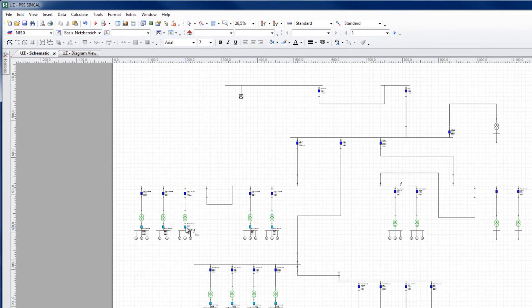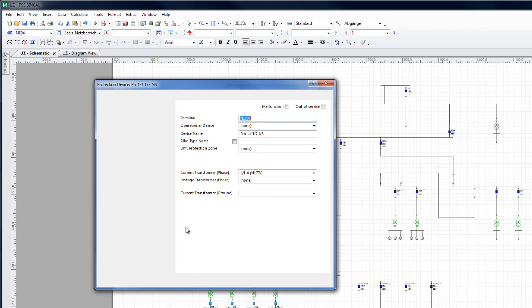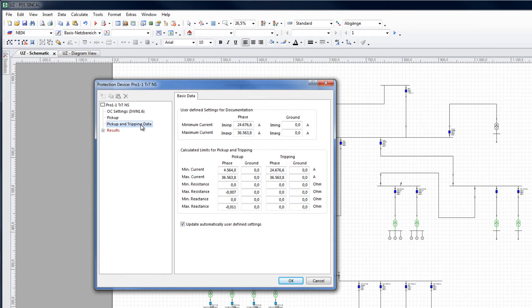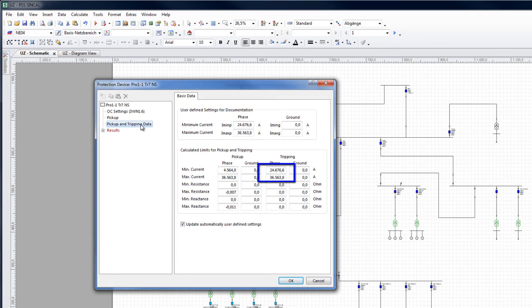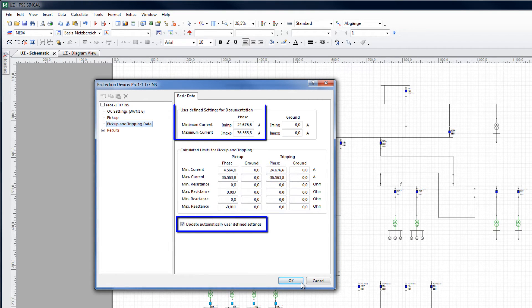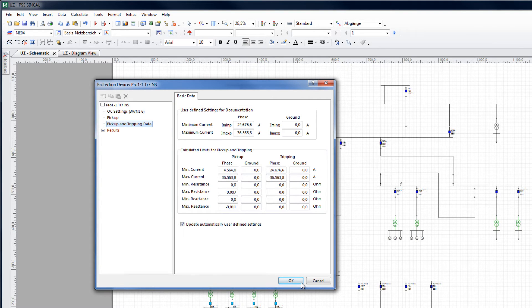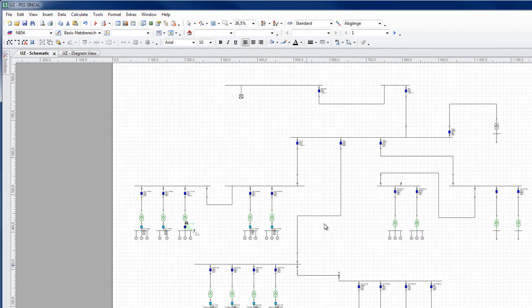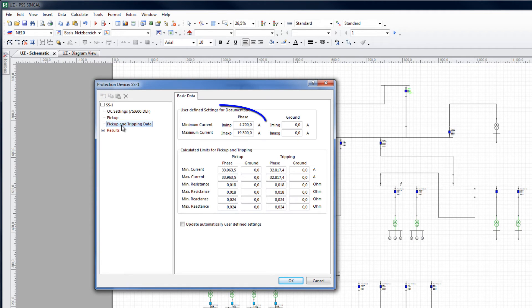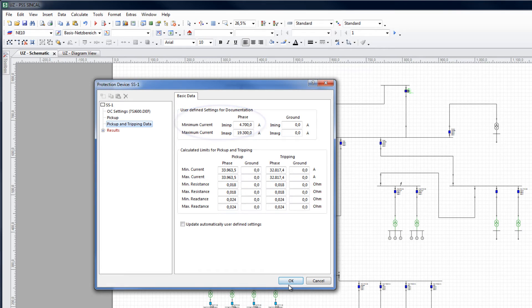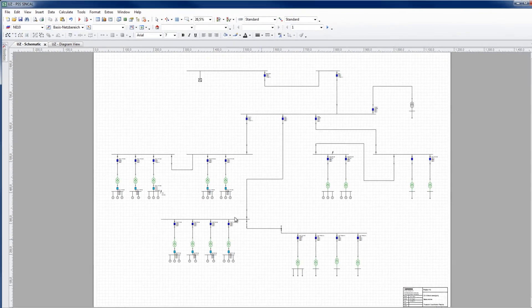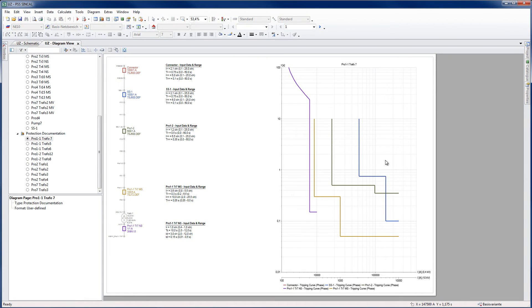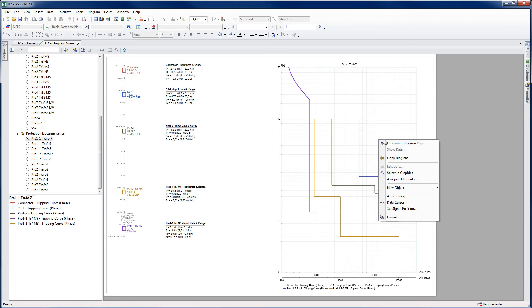The minimum and maximum seen by the device so far are registered in the pick up and tripping data results tab. To use these values in the documentation click here. Alternatively, a short circuit band used for the protection documentation can also be entered manually. For coordination, this band can now be displayed in the grading diagram.